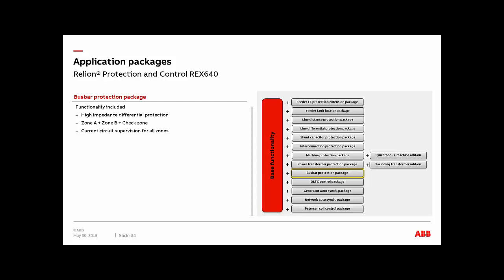But for a regular bus, we do have to use a high impedance differential protection, and we do have the option of zone A, zone B, plus a check zone, which will give you more security in your trip logic if you want to go this route as well. You also have current circuit supervision for all the zones included in the relay. This is more of a control function of the relay.